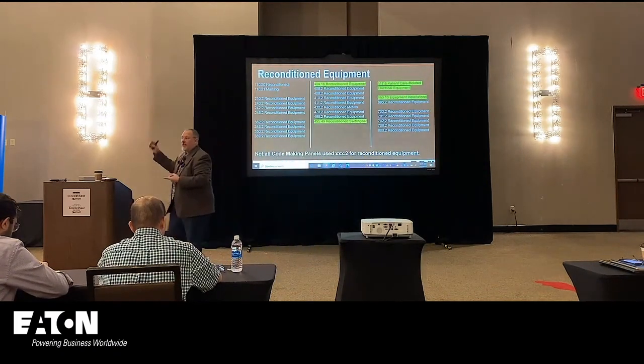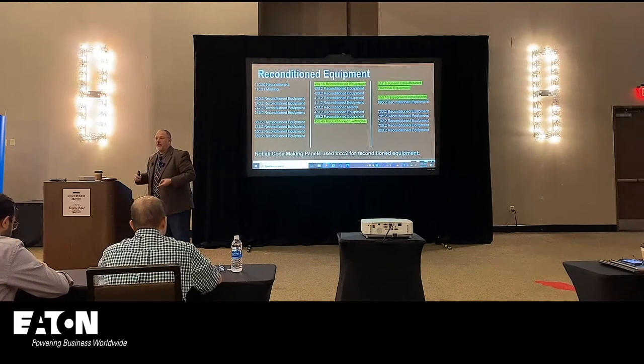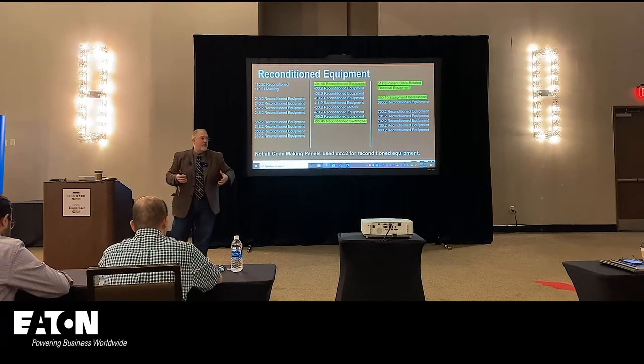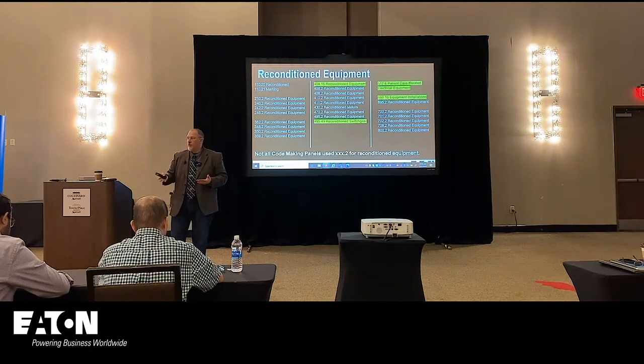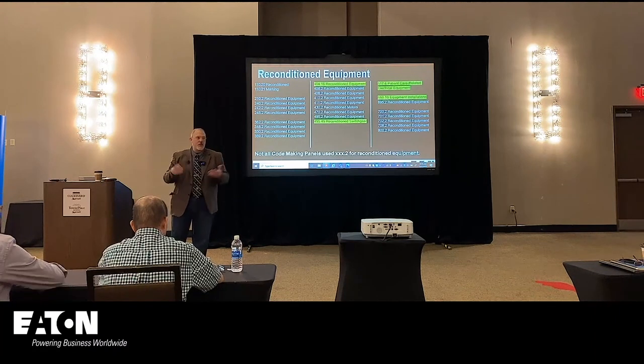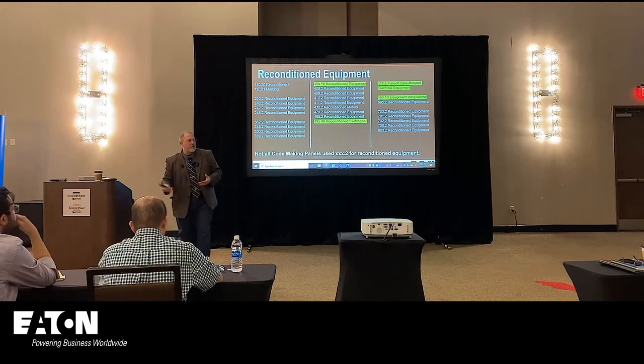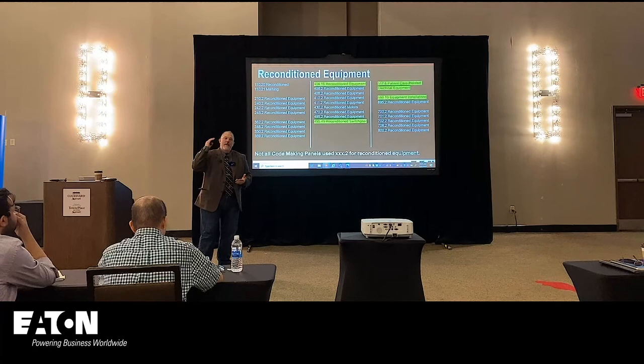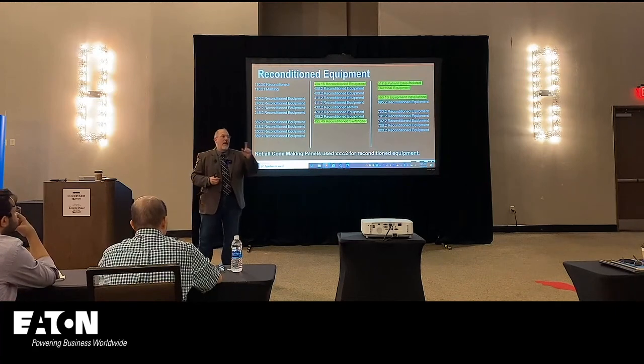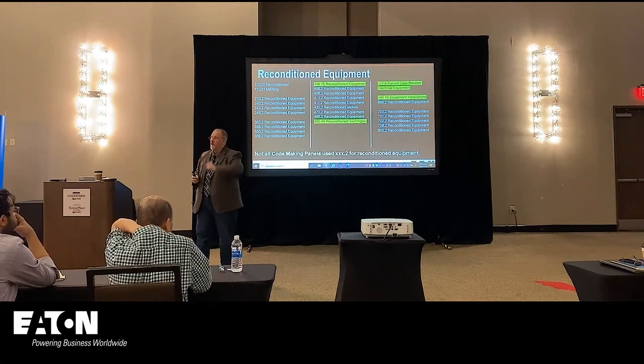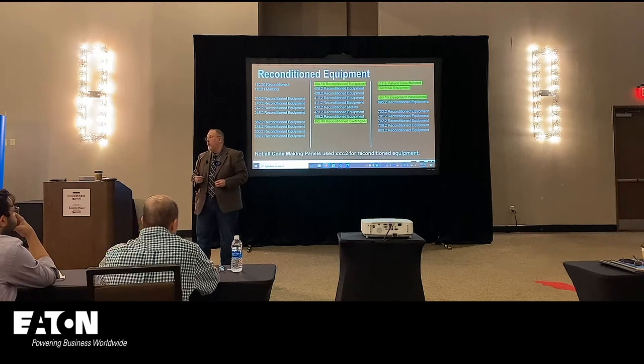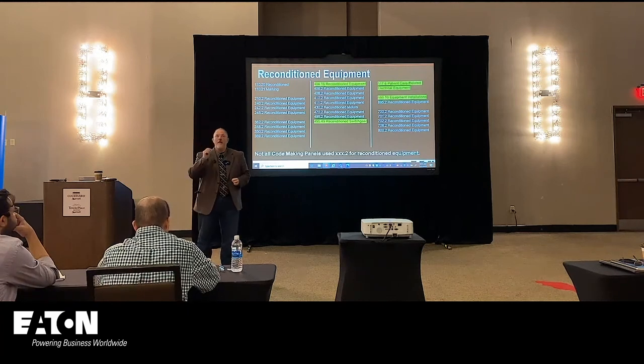If you take that computer apart and you put it all back together again, yeah, you have the shell of an HP computer, but it's no longer HP, it's now yours, right? Same thing with electrical distribution equipment. If you recondition a switchgear, a power circuit breaker, whatever it is, we want your name on it, and you've got to remove the UL label or make it unreadable.